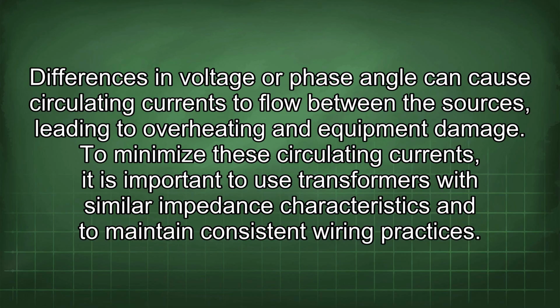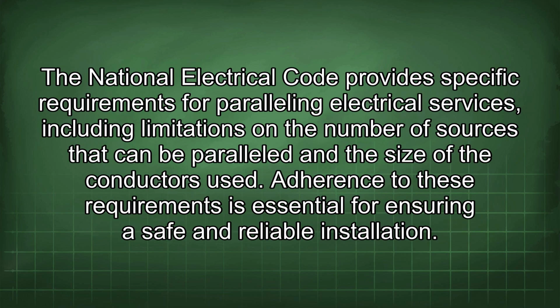Differences in voltage or phase angle can cause circulating currents to flow between the sources, leading to overheating and equipment damage. To minimize these circulating currents, it is important to use transformers with similar impedance characteristics and to maintain consistent wiring practices. The National Electrical Code provides specific requirements for paralleling electrical services, including limitations on the number of sources that can be paralleled and the size of the conductors used. Adherence to these requirements is essential for ensuring a safe and reliable installation.